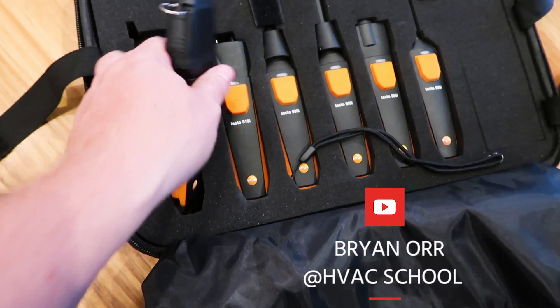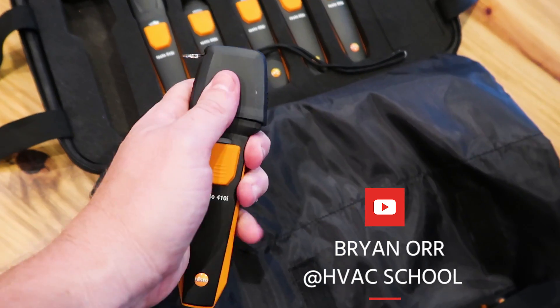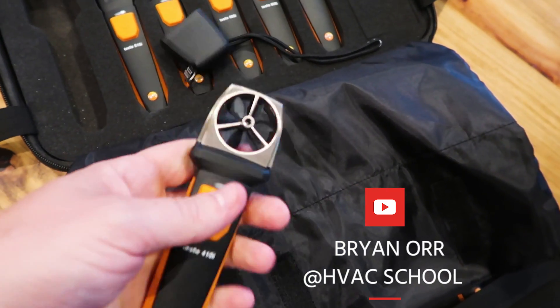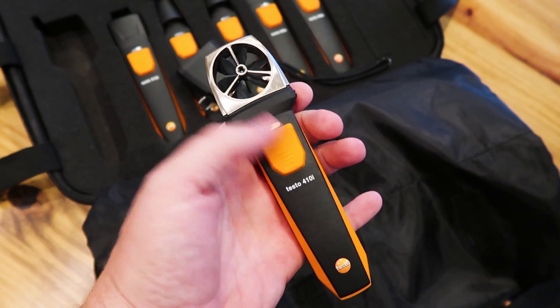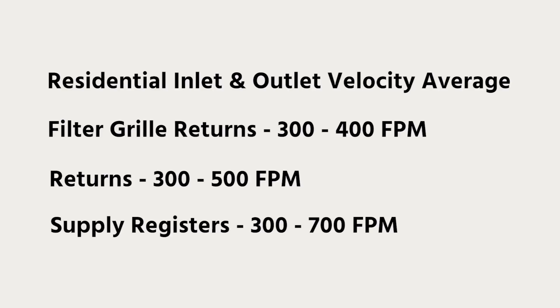Hi, I'm Brian Orr with the HVAC School Podcast. I'm doing this video to show you the Testo 410i and how you can use it to measure velocity and then convert that into volume flow. In general, in a residential air conditioning supply duct, we want to see velocities anywhere from 300 feet per minute to about 700 feet per minute.